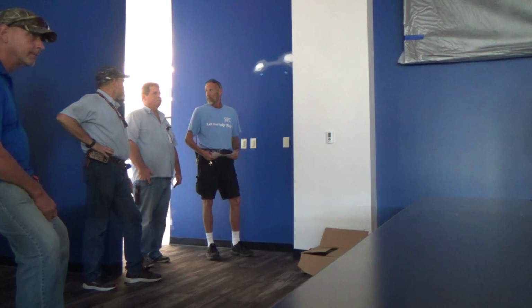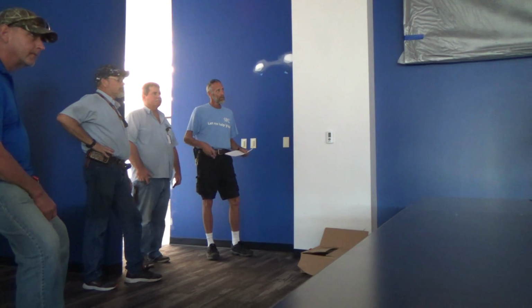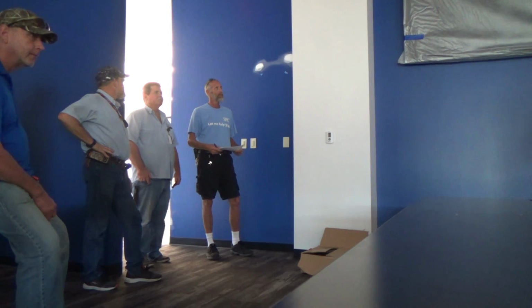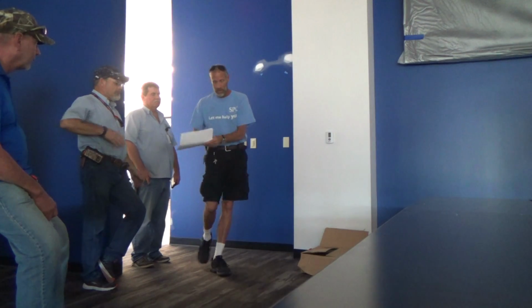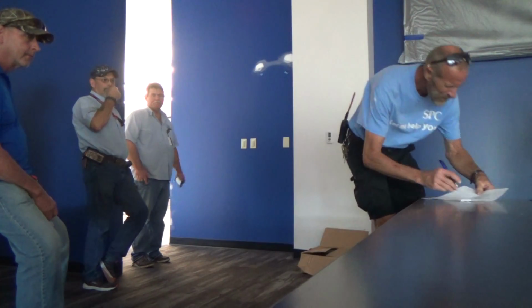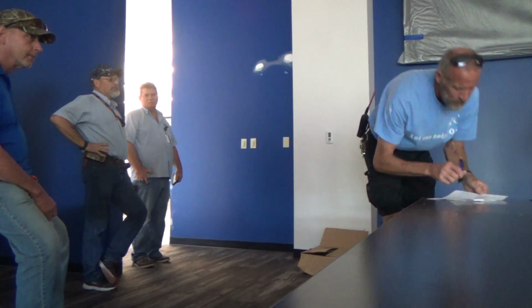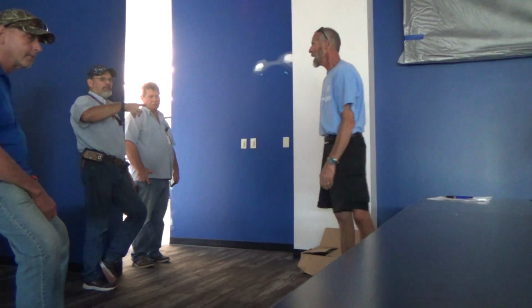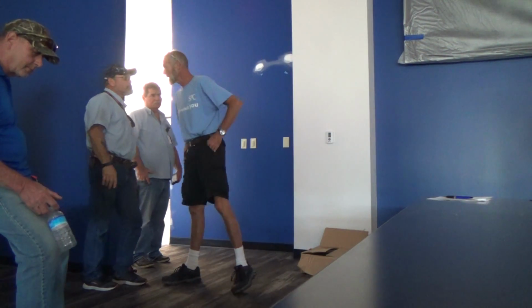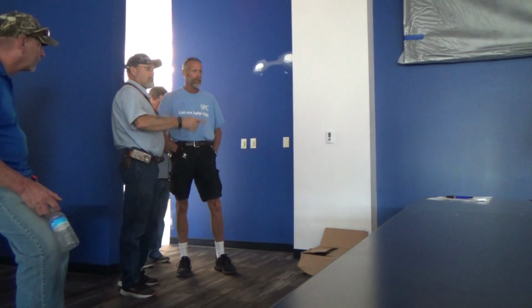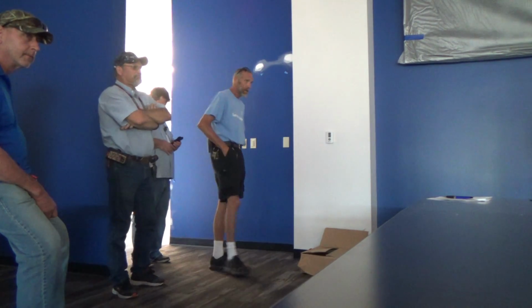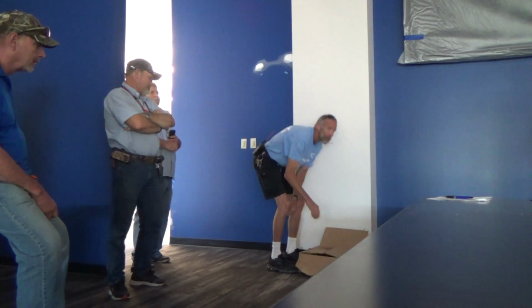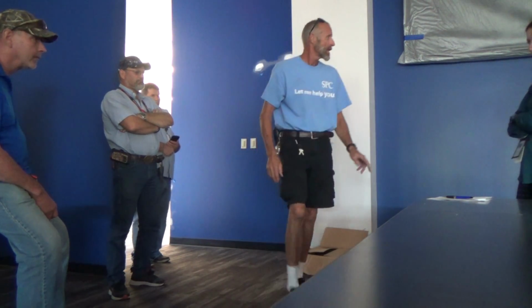Can we change that? You can. It's Florida Building Code is why we do that. But if you have an area that you need to change, it's a setting, so it's definitely changeable. If you have areas that people are constantly going into, and the lights won't come on, they have a hard time finding the switch, you can absolutely make that area an auto on. Or vice versa, if people are complaining about having to hit the button, we get that sometimes.